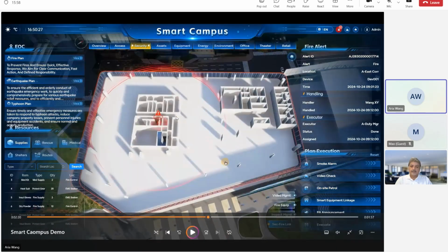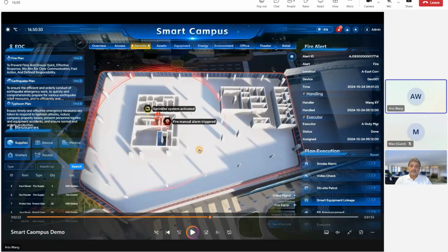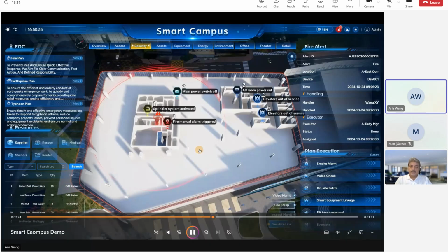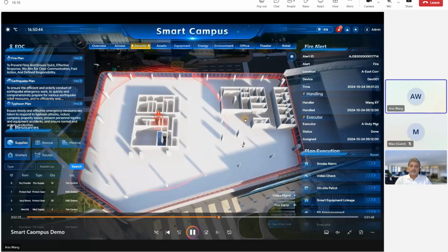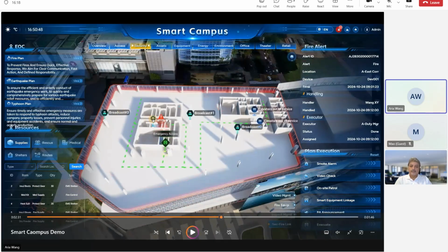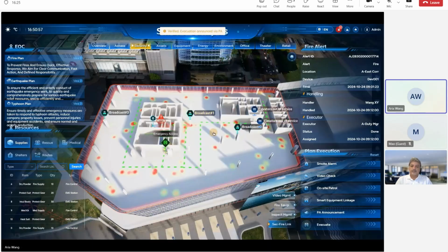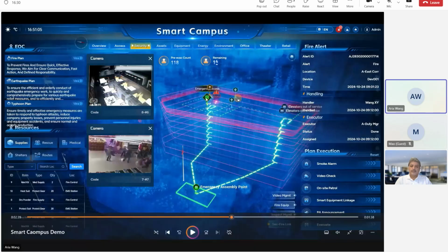if we have the remote control of all the devices and the elevator, the system can do the fire protection automatically. The first one is sprinkler activation, and then shut down the elevators, cut down the AC room power. And the fifth is the broadcast. And last one is evacuation.